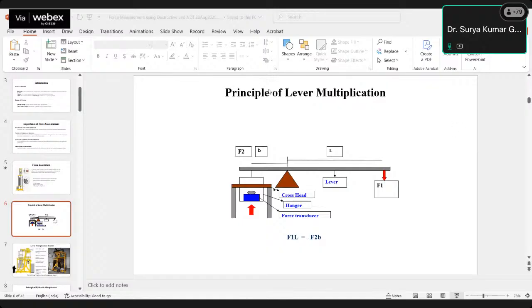It is a fully automatic force machine, and we can control loading and unloading using a motorized controller. Calibration is performed using ISO, IS and ASTM standards, and it can be done in both compression and tension mode.